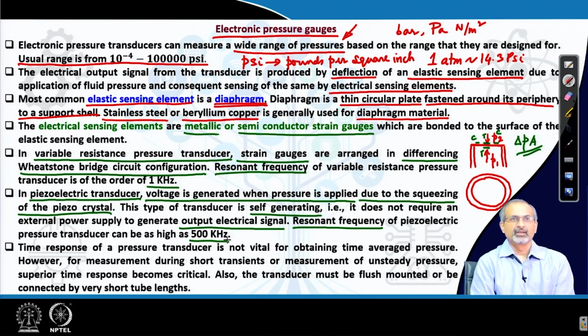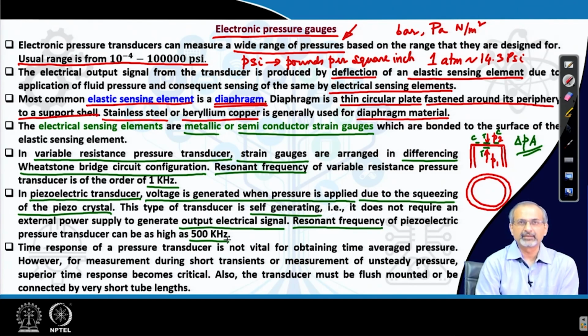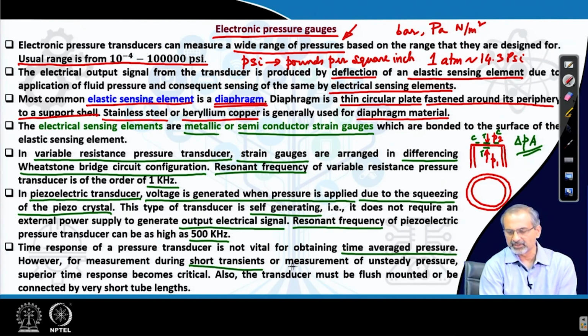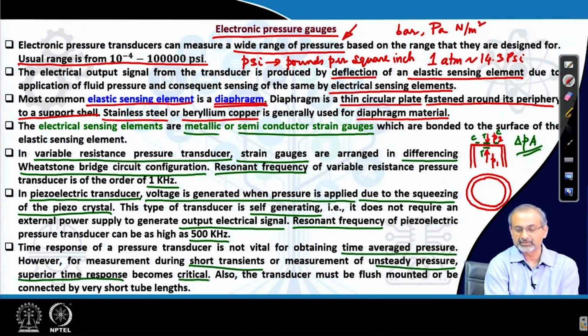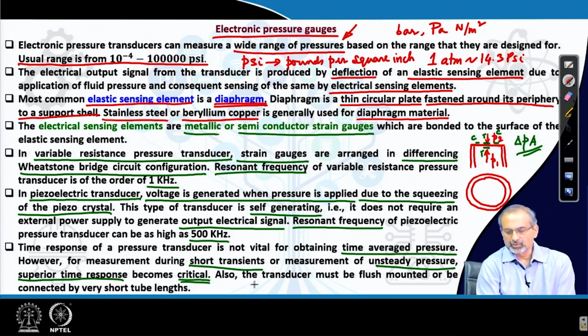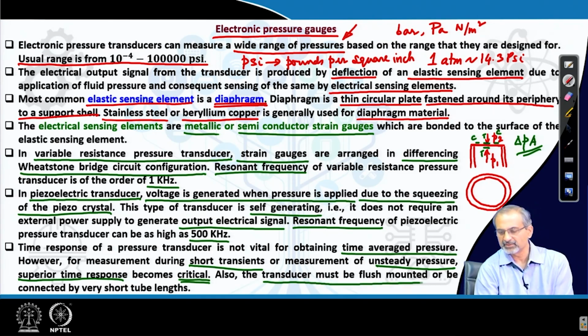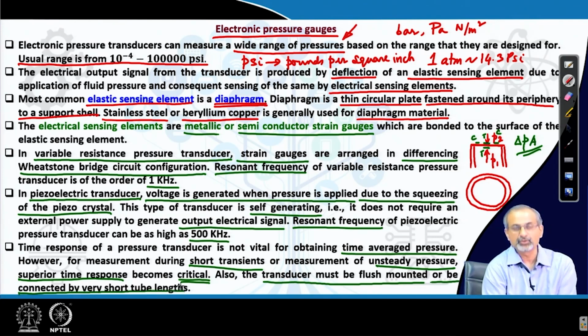The time response of a pressure transducer is not vital for obtaining time average pressure. However, for measurement during short transients or measurement of unsteady pressure, superior time response is absolutely critical. Also, when you are looking for superior time response, the transducer must be flush mounted or be connected by very short tube lengths. That means the point at which you are recording pressure, the transducer needs to be absolutely flush mounted to that point or very close to that point, but certainly not at a far off point connected using a pressure tubing. That is a very faulty way of measuring time dependent pressure.